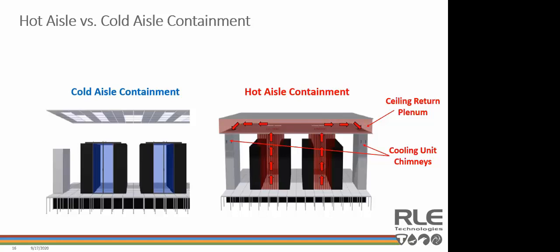Hot aisle containment, on the other hand, contains the warm server exhaust air in the hot aisle. When using hot aisle containment, the warm air is usually contained from the floor to the ceiling with vents in the ceiling to allow the warm air to be pulled into a return air plenum, and then that warm air gets sucked back into the cooling units for reconditioning. The cooling units are typically modified with a chimney on the top of them, which allows the warm air to be pulled directly into the cooling units from the return air plenum. Because of this, cold aisle containment is usually easier to implement in older legacy data centers due to the fact that it doesn't require a ceiling return air plenum.